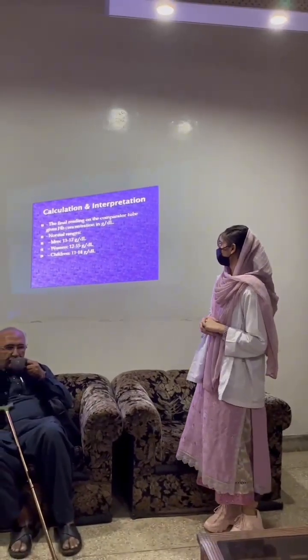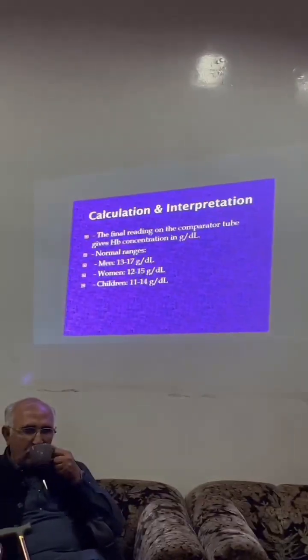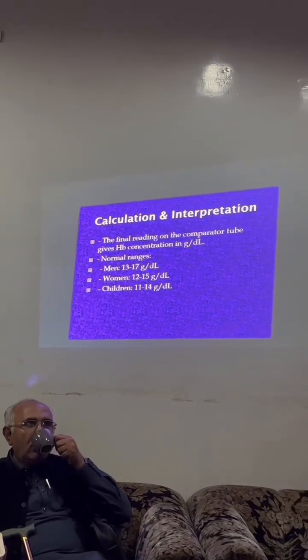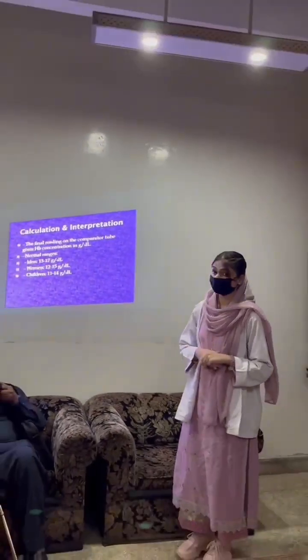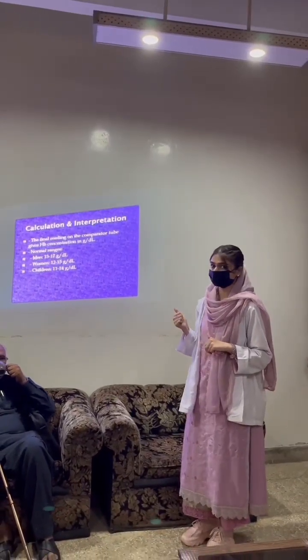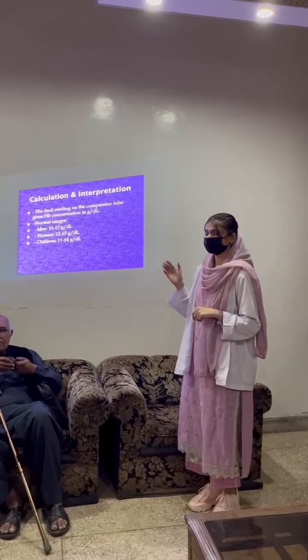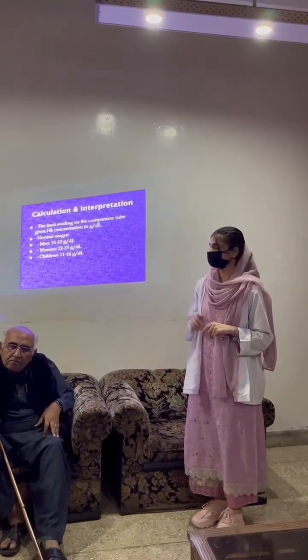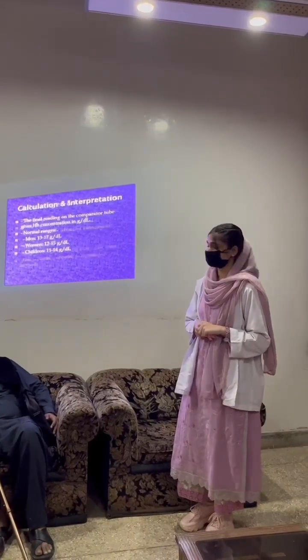The final reading from the comparator tube gives the hemoglobin concentration in gram per deciliter. The normal ranges are: in men, 13 to 17 gram per deciliter; in women, 12 to 15 gram per deciliter; and in children, 11 to 14 gram per deciliter.